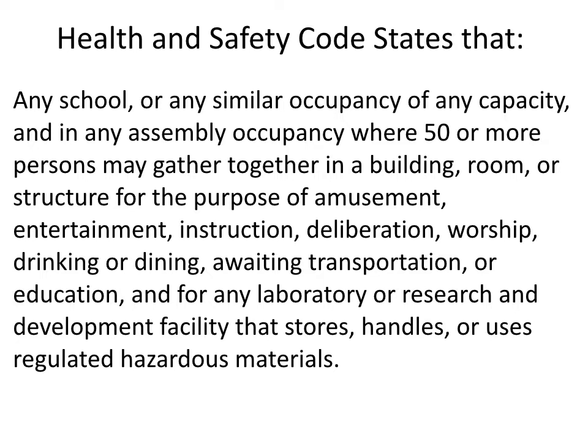So this is kind of the definition of an assembly. 50 or more where people gather in a room or structure for the purpose of amusement, entertainment, instruction, deliberation, worship, drinking or dining, awaiting transportation or education, and then for any laboratory or research and development facility that stores, handles, or uses regulated hazardous materials.